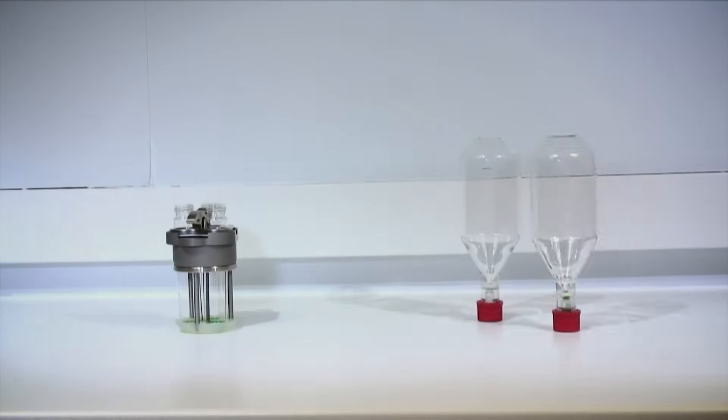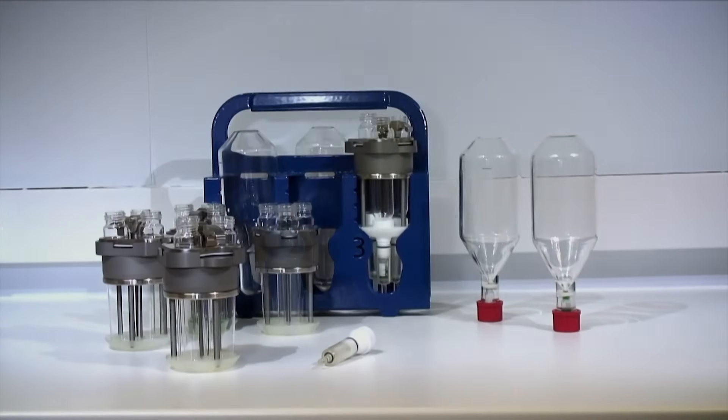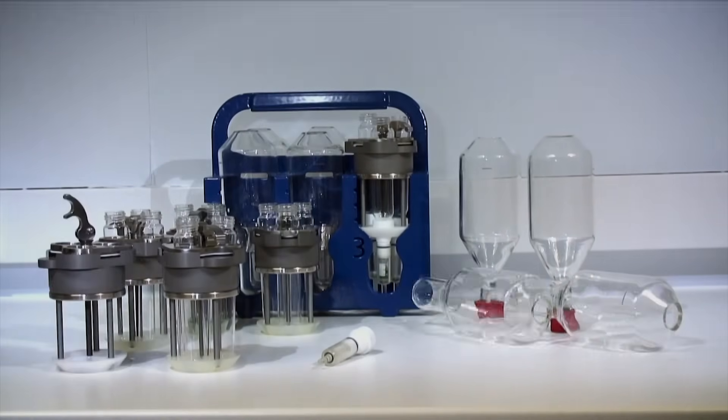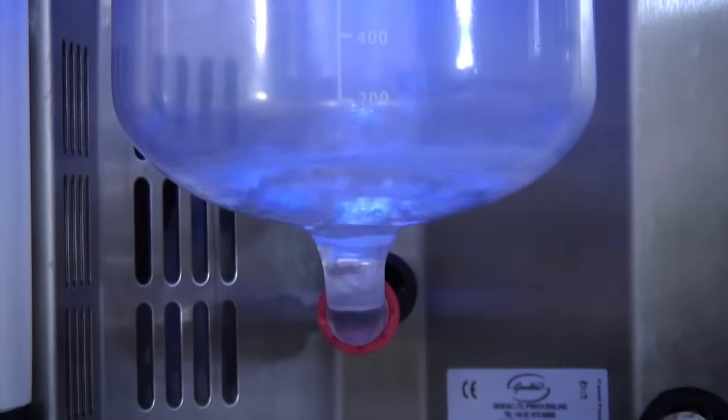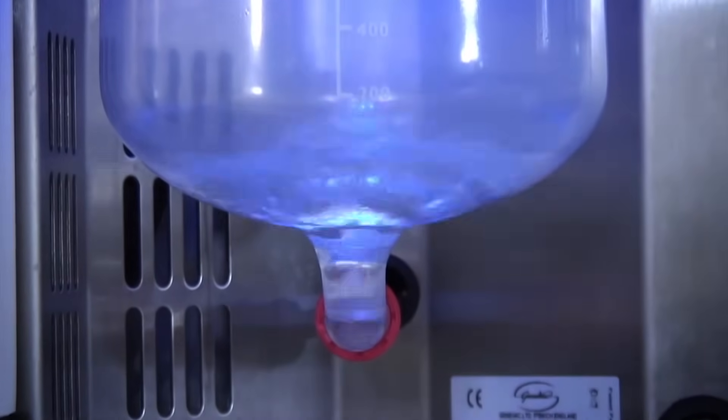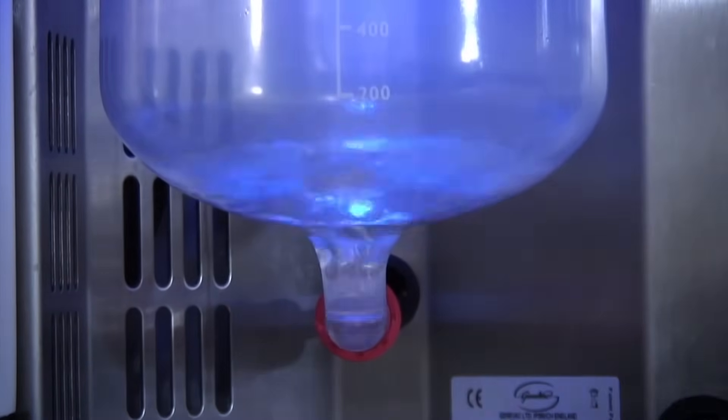The Rocket evaporation system is designed primarily for large volume parallel evaporation. The samples are spun and, as they boil, vapors are drawn to the cold trap, which condenses the vapors to a liquid.